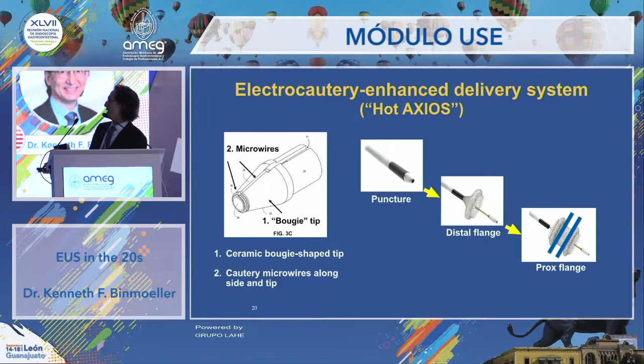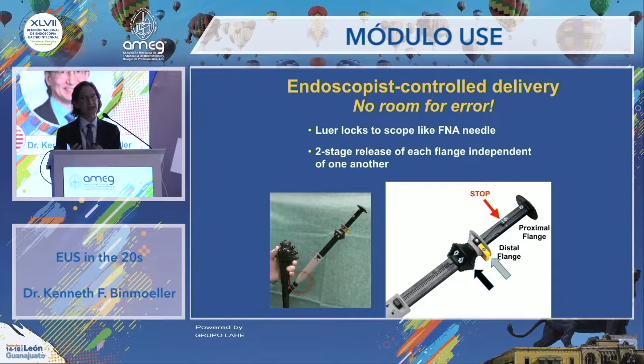So we puncture, we deploy our distal flange, and then immediately our proximal flange. And the distance here is only 1 centimeter. And for that reason, there is no room for error. The delivery must be very precise and 100% accurate, and therefore it should be endoscopist controlled. So this locks, just like an FNA needle, to the biopsy port of the echo endoscope. And there is a two-stage release as a safety factor. You release the distal flange completely independent of the proximal flange. And there's a full stop in between the deployment of the distal flange and the proximal flange with a click in between. So it guarantees that you don't accidentally deploy the entire stent.